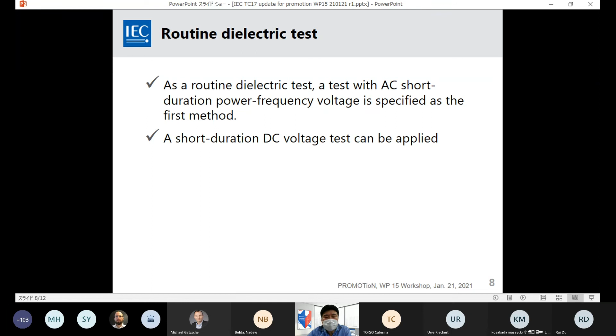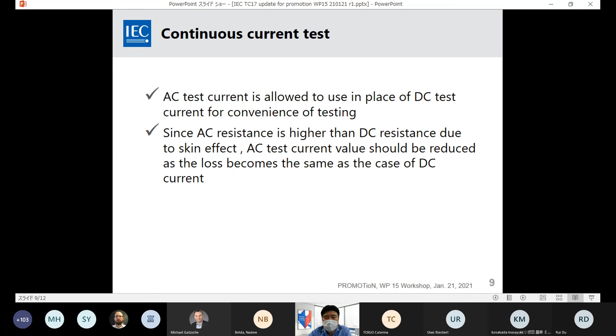Concerning continuous current test, in the continuous current test, AC test current is allowed to be used in place of the DC test current for convenience of the testing. Since AC resistance is higher than DC resistance due to skin effect, AC test current values should be reduced so that the loss becomes the same as the case of the DC current.